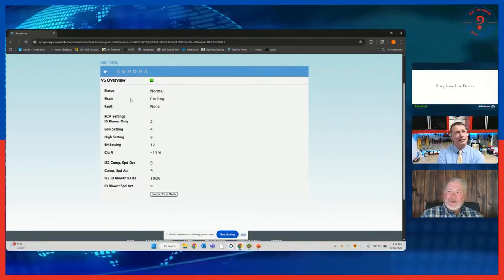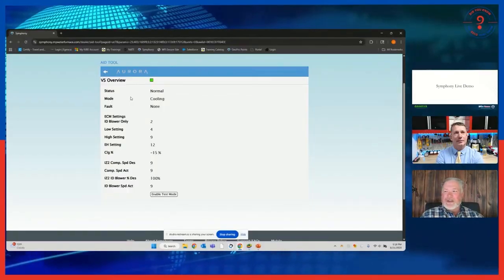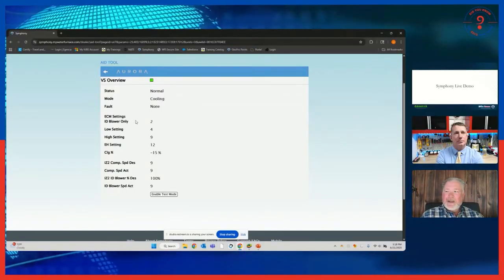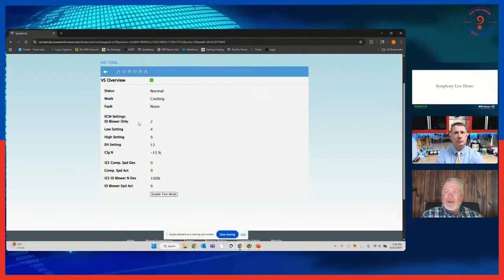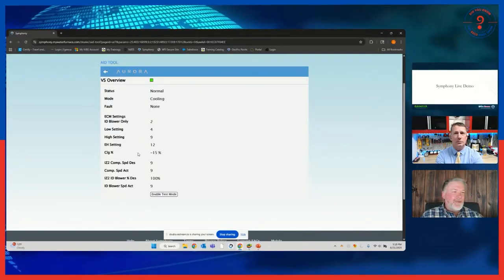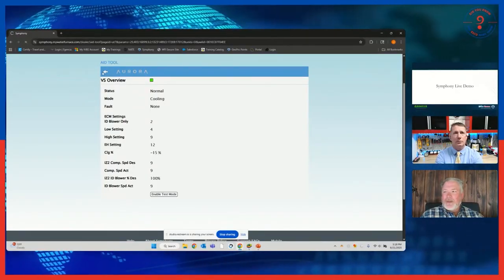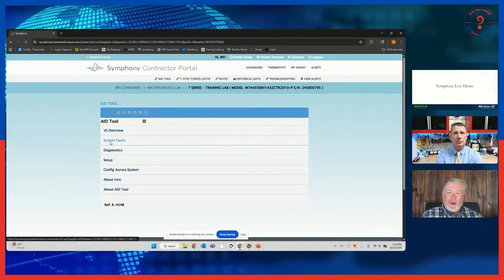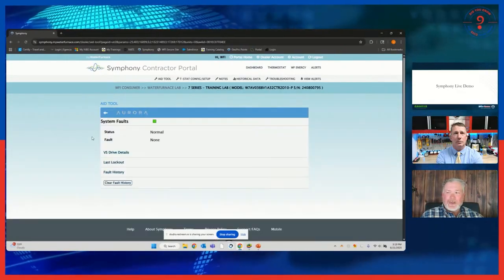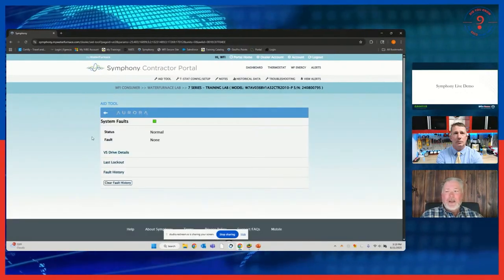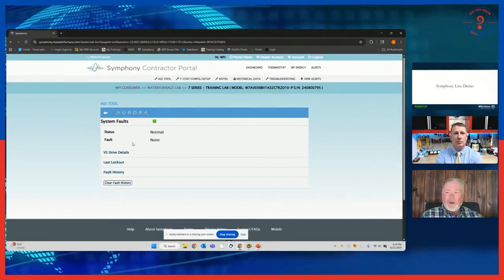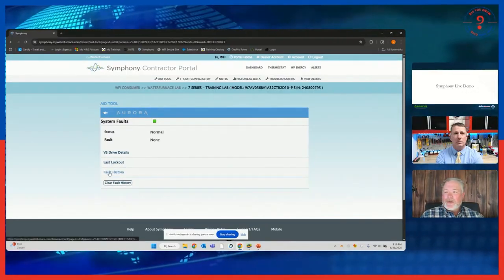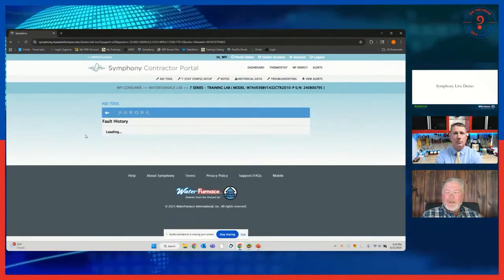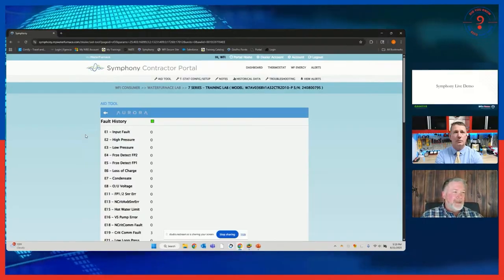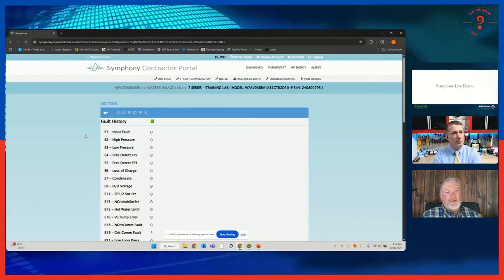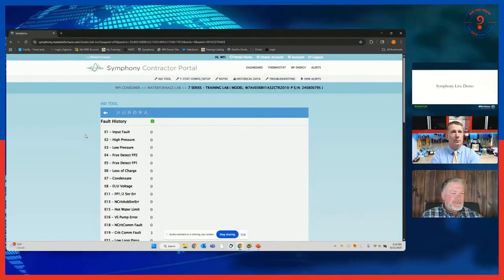So this is kind of an overview screen, so I can see what the unit's doing right now - what blower it's on, what setting it is, basic information. Below that, I have system faults - if the system was faulting right now, which it's not, it would tell me what that fault is and what mode it's in. I can also go into fault history and see what that unit has faulted out on in the past. We use a fault retry system with our equipment.